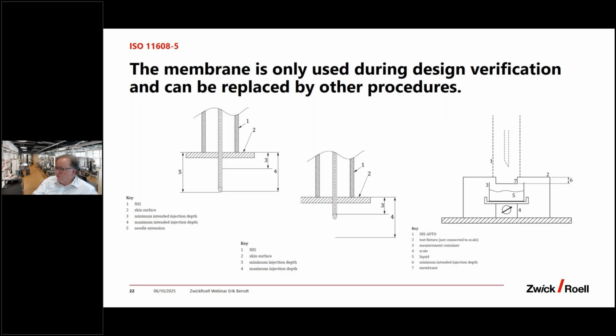Some of my customers or people who are contacting me say it's not quite clear, perhaps referencing, because there's also an informative chapter at the end where there is this white picture with the balance and the membrane inside. And some people are now saying, oh, now I have to do all my testing with this membrane. Short answer to this, no, this membrane is only used during the design verification, and in the standard it is also written, it's only one sentence, that you can also use other methods to do this. If you have topics with this, please contact me.